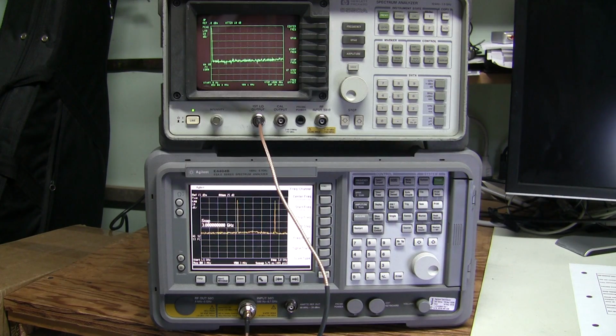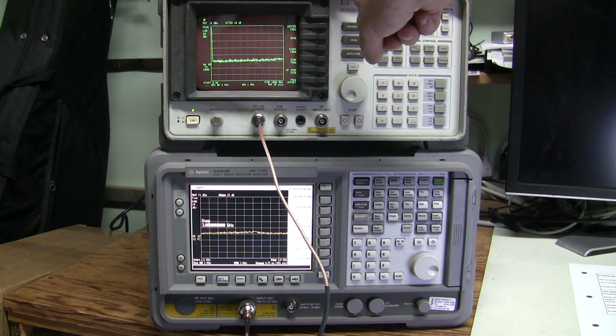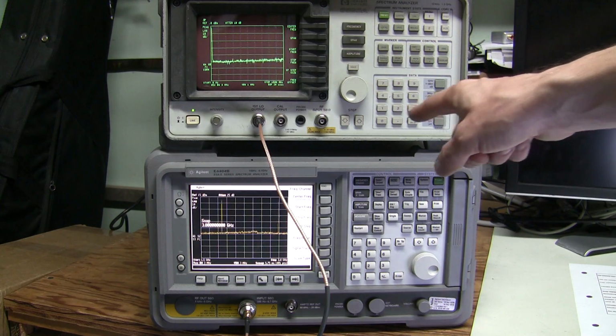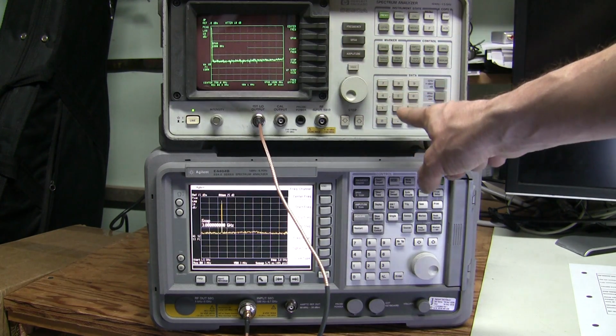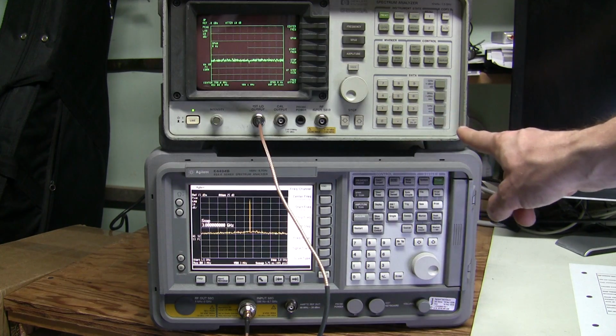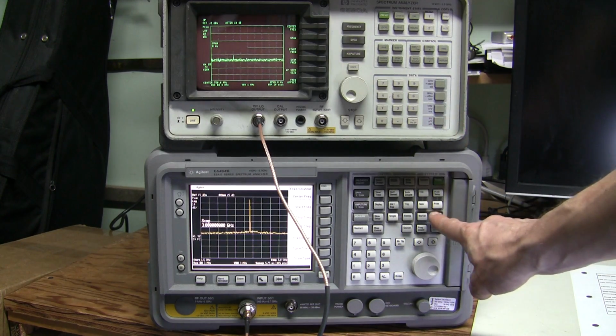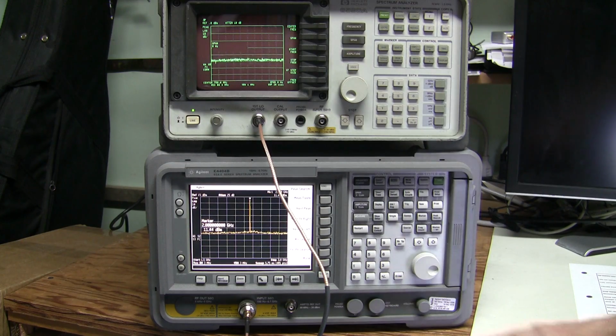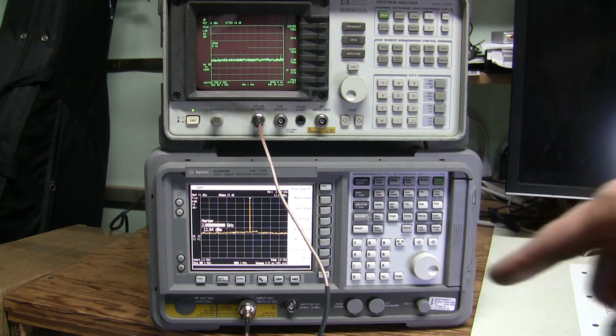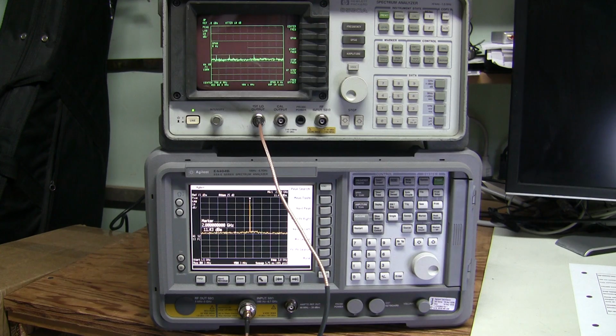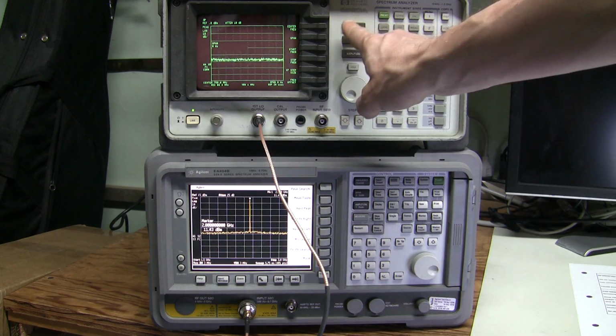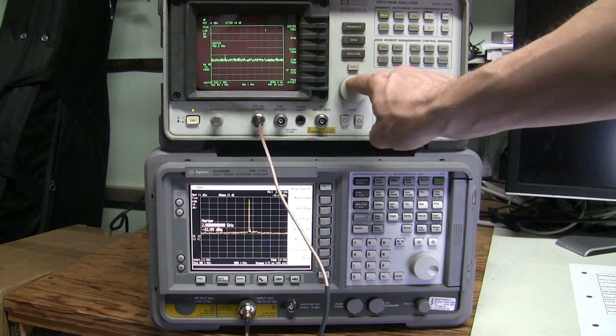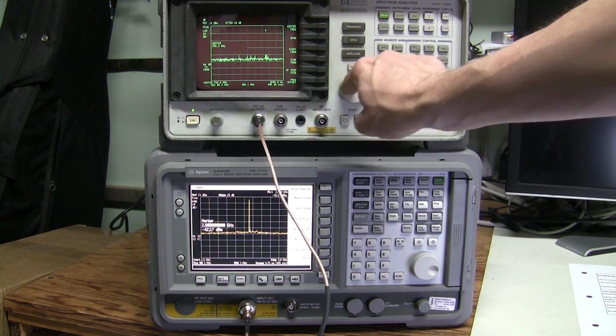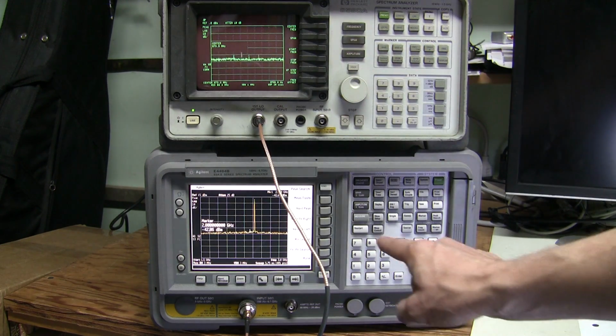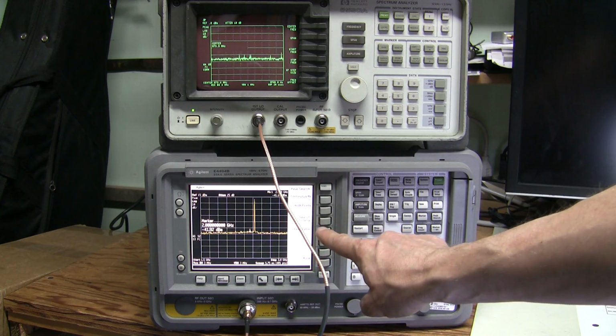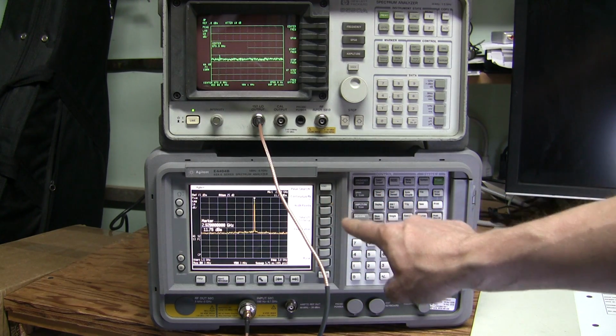And there you go, it's jumping around because the analyzer is sweeping all the way across this range. We can stop that by setting 0 span. So now it stays put. We can do peak search at 2.8 gigahertz, about 11.5 dBm, looks fine. So now we should be able to tune here up and down and up. Looks fine, and we can set this peak search to follow this continuous peak on.